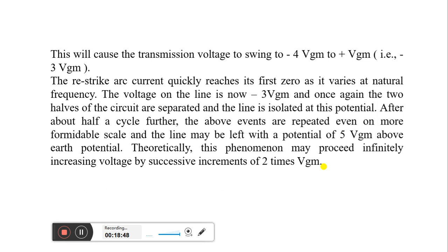So what will happen? It is clear that if the gap breakdown strength does not increase rapidly enough, successive restrikes can build up a dangerous voltage in the open circuit line. However, due to the leakage and the corona loss, the maximum voltage on the line is limited to 5 VGM only. So what this is telling is that if restriking takes place at the opening of the line, and sufficient dielectric strength is not able to develop across the circuit breaker contacts, this process will keep on repeating, and a very high voltage will develop across the line. But due to the severity of the dangerous condition, this voltage rise is limited to a maximum value of 5 VGM only, and if the voltage increases beyond this value, then some other precautionary measures are taken so that the transmission line remains in healthy condition.